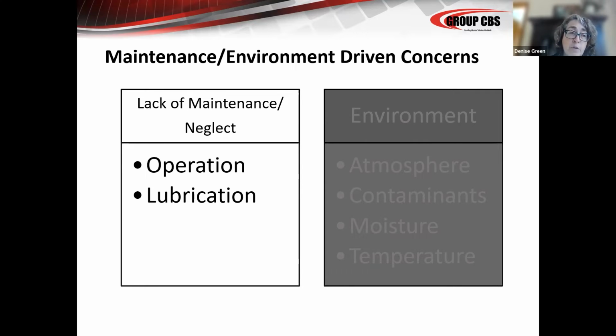The next component is lack of lubrication. So most lubricants that are on the market now that are recommended by the OEMs and NFPA 70B and the NETA MTS recommend that equipment be lubricated every 3 to 5 years, unless it's in an environment that requires it more quickly. The reason for that is the components inside the lubricant products that we use are only good for 3 to 5 years. And the 3 to 5 years is in perfect conditions. So if you have an area where those conditions are not perfect, that lubrication is not going to perform as intended over extended time periods and in poor environments.